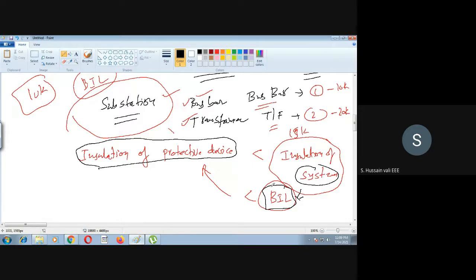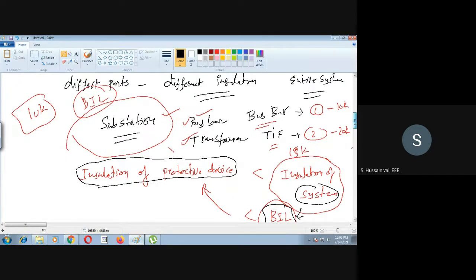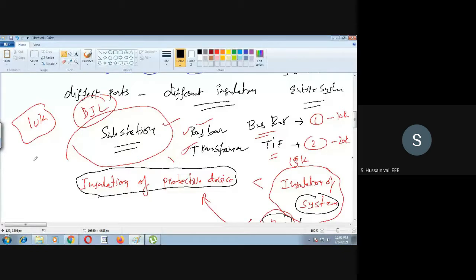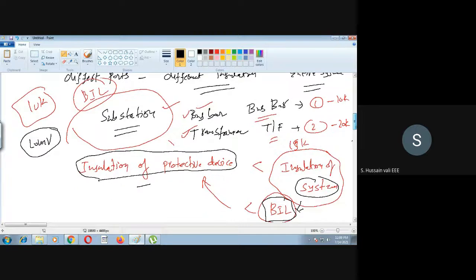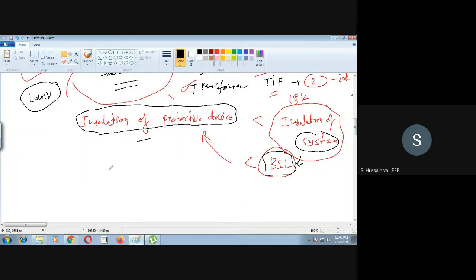How do you calculate this BIL? Generally, whichever device has the lowest insulation among all the devices, we take that as the BIL. Otherwise, this protective device cannot protect. Generally it is represented in units. Which units? It's represented like this: 1.2 by 50 microseconds. The units of BIL is something like this. What is this value? I will show you.